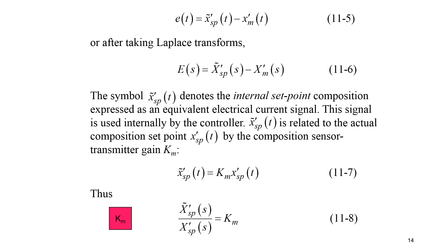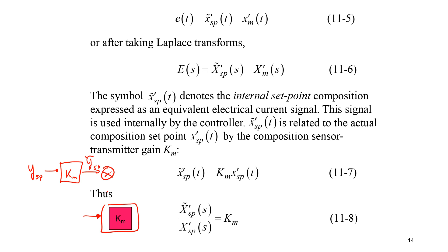For the measurement, it translates concentration into a signal — in this case a milliamp signal. We're going to assume the sensor is fast, with time constant equal to zero. We use KM to translate the set point Y-SP into Y-tilde-SP, so that the measurement and the tilde Y-SP are in the same units for comparison in our error calculation going into, for example, our PID controller.